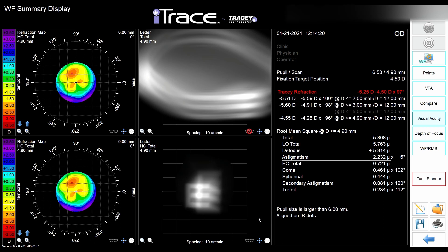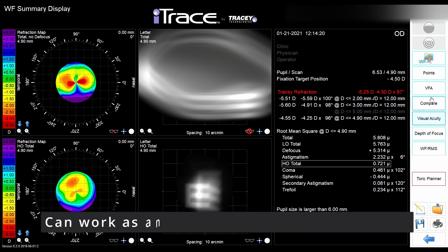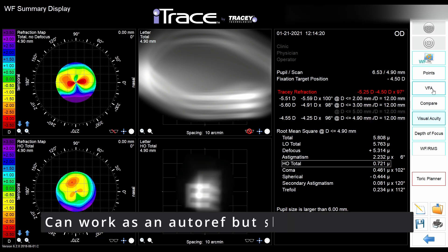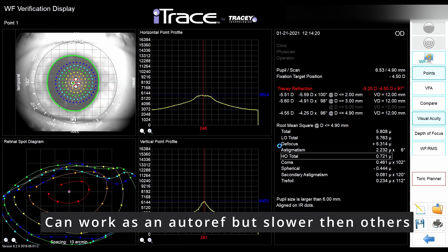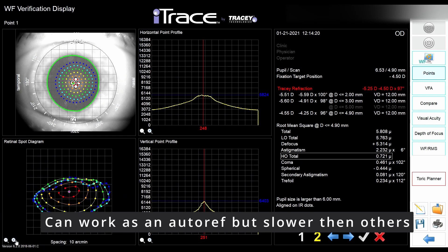Can this machine be used as a standalone autorefractometer? The answer is yes, but it's not as fast as autorefractometers from Topcon or Nidek. Unless you're a super premium cataract or refractive surgery center without many patients, it can function as an autorefractometer. But if you have plenty of other patients, I would suggest buying a separate machine.